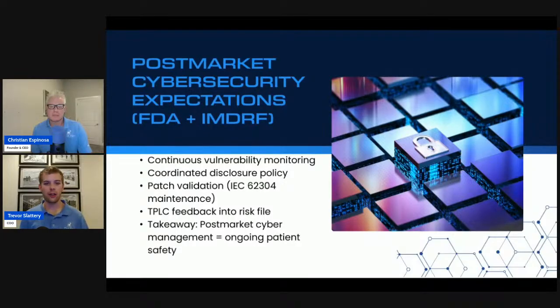Now, through any information that we're collecting, be this through our CAPA, be this through maybe third-party research, or through notifications from the FDA, CISA, we want to make sure that we're collecting all of this feedback, integrating it into the risk file, and having a clear process on how we are actually responding to threats that come up in the post-market. How are we using this information we're collecting to provide a better version of the device in the future? We want to make sure that we're using post-market cybersecurity management to ensure that we have ongoing patient safety and that the security of the device does not start slipping once it's out on the market. That's right. Cybersecurity needs to be considered from design to disposal. All the way through.